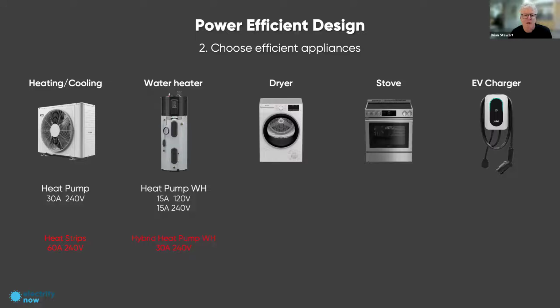That's an important one. When it comes to water heating, we have some really good options now. There are two options for 15 amp water heaters. For reference, a typical electric water heater is 30 amps, and the hybrid water heaters, which are a mix of heat pump and electric, are also 30 amps. But you can get 15 amp heat pump water heaters, in either 120 or 240 volt versions. That takes a big chunk out of what you need. They'll still deliver all the hot water you need, but you're being miserly, so to speak, on your amperage.